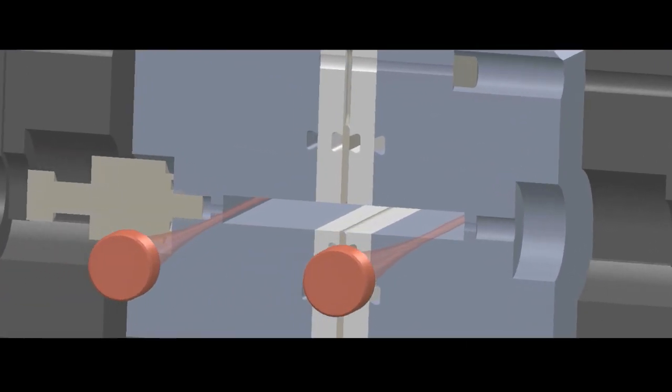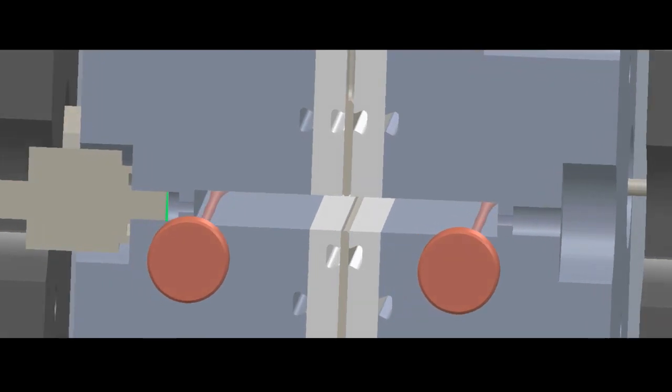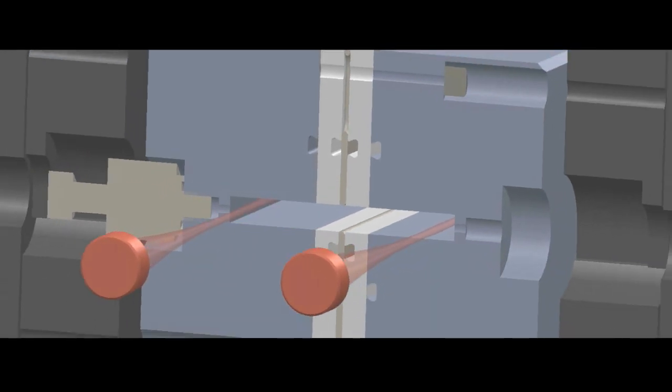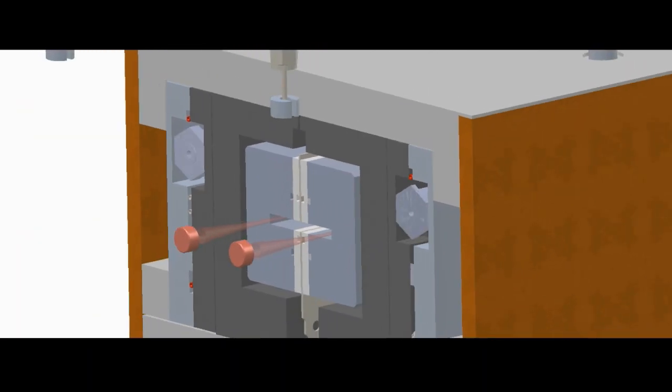During a measurement cycle, two ring-down cavities record the progress of the chemical vapors down the diffusion column at the core of the instrument. Because of different gas and surface interactions, each molecular species has a unique trajectory down the column. Onboard data processing analyzes the recorded diffusion trajectories to calculate the concentrations of the chemical present in the vapor sample. This innovative combination of cavity ring-down and diffusion time of flight enables the Aroma instrument to offer performance that is unmatched in the industry.